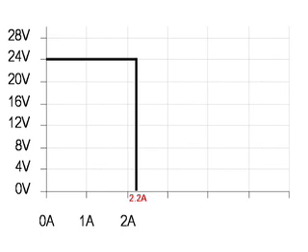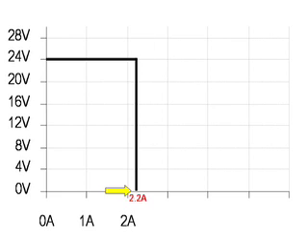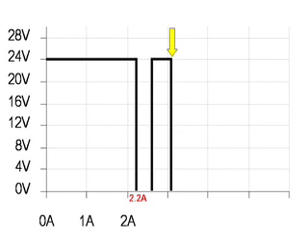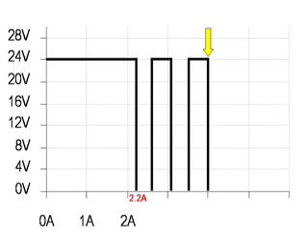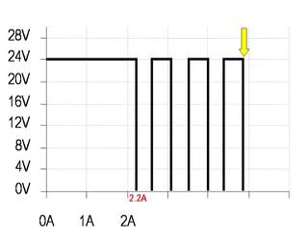With the hiccup mode power supply, an overload is not handled in the same manner. Once again, the voltage would be 24 volts DC at zero current, and as the current increases above its rated value, the power supply will shut down, wait a small period of time, and then attempt to start again.